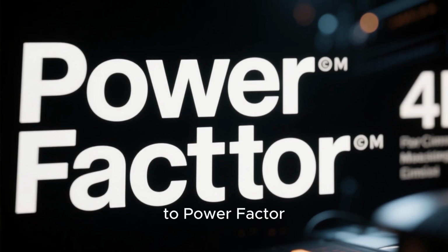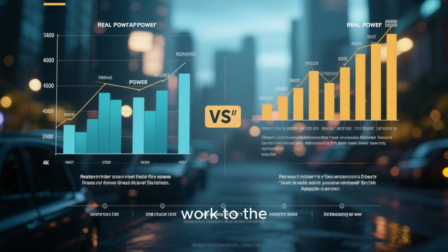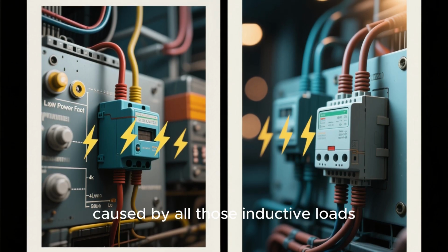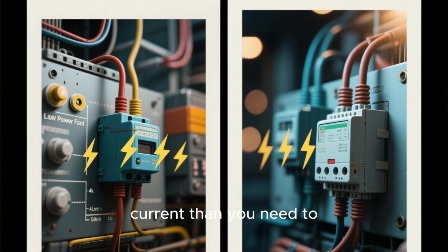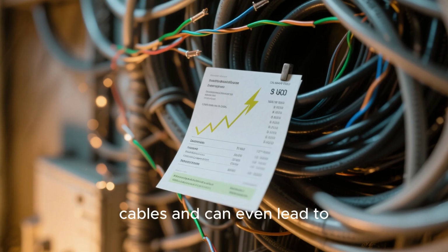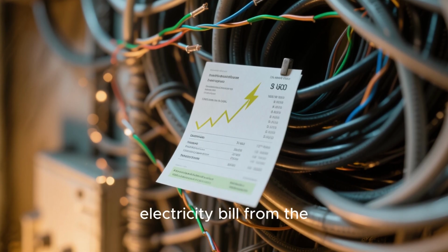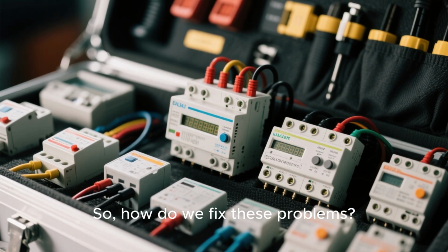Let's circle back to power factor because it's a huge deal. Power factor is the ratio of the real power doing actual work to the apparent power being supplied. A low power factor, caused by all those inductive loads, means you're drawing more current than you need to. This forces you to use larger, more expensive cables and can even lead to penalties on your electricity bill from the utility company. So, how do we fix these problems?